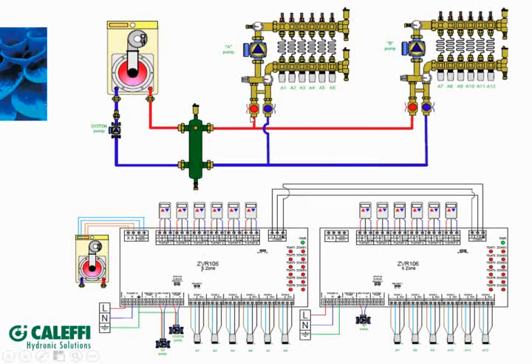Now, one thing to keep in mind too, and I don't think I have a slide on this. If you did have 2 boards, let's say you had 12 zones and you only had 1 secondary pump, at that point your single secondary pump would need to come off of probably the system pump contacts, because the system pump always runs when there's any heat demand at all from either board. So you would need to use that set of contacts for both your secondary pump and your primary pump. It's kind of a special case, but we'll clearly show that in the wiring guide.